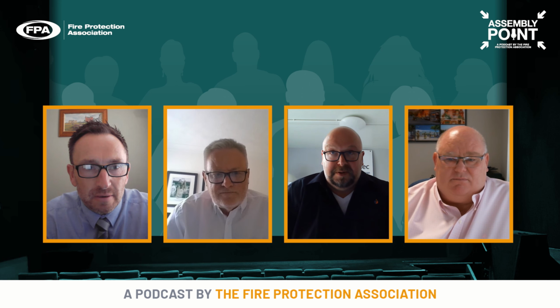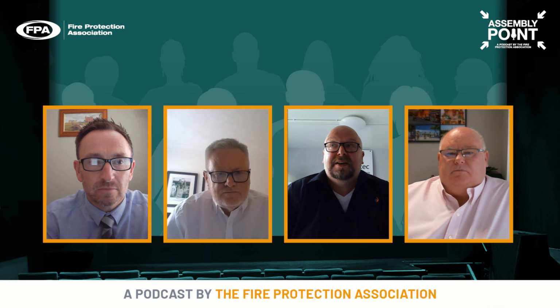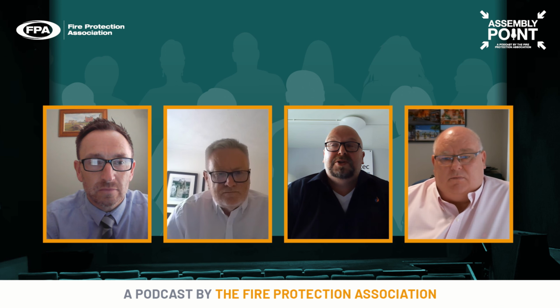And just one point on the consultation, and both of the sprinkler standards we've been talking about, there's a huge bit in consultation that says that you should consult with the building control officer, fire brigade, water authority, insurance, and so on. So the principal consultant should do all that before actually spitting out the spec. So that's all I can really say. The other thing I would say is that if a consultant's not sure what to use, I always refer them to BS 5306 Part 0.